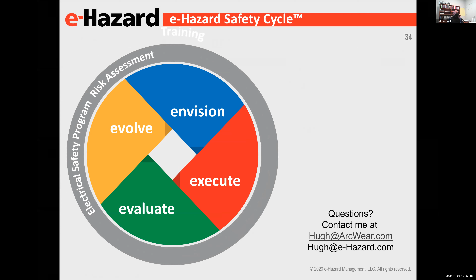And so just at eHazard, we like to use our E's, and we want you to have basically a Deming model for everything in your program. You want your electrical safety program to envision, execute, evaluate, and then when you need to change it, you evolve it. Same thing with your risk assessment, your arc flash studies. Periodically, go back and look. Like right now, those 1584 changes will change some of your equipment. So go back either to your previous company that did that, or go to eHazard, or get with your engineers and go back and look at 1584, recalculate with this new version, because there will be some places where it will affect your PPE levels.